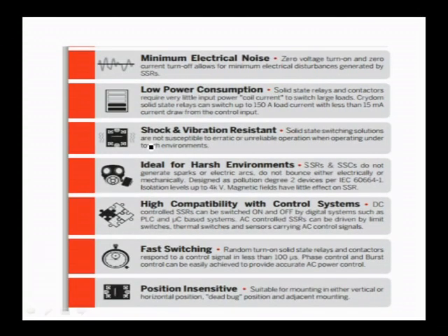This again lists the same advantages: low power consumption, zero voltage turn-on, zero current turn-off, allowing minimum electrical disturbance. Again shock and vibration resistance, reliable operation under tough environments. Ideal for harsh environments, they do not generate sparks or electric arcs, and they do not bounce either electrically or mechanically. Designed as pollution degree 2 devices, which as specification you need not worry about. Isolation levels are up to 4 kV. Magnetic fields have little effect on solid state relays.